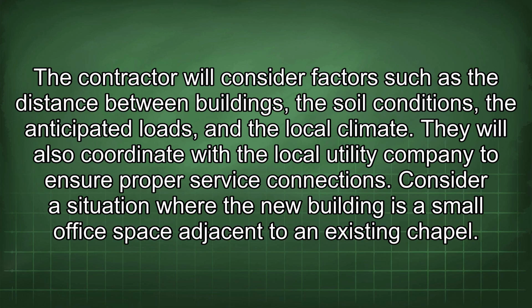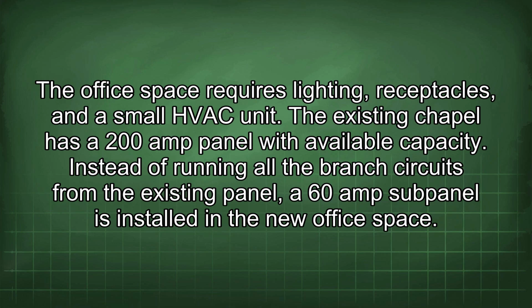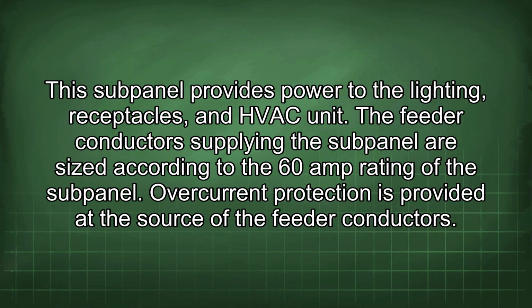Consider a situation where the new building is a small office space adjacent to an existing chapel. The office space requires lighting, receptacles, and a small HVAC unit. The existing chapel has a 200 amp panel with available capacity. Instead of running all the branch circuits from the existing panel, a 60 amp subpanel is installed in the new office space. This subpanel provides power to the lighting, receptacles, and HVAC unit.